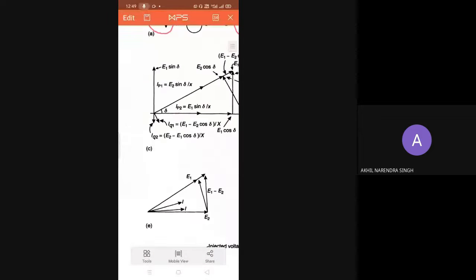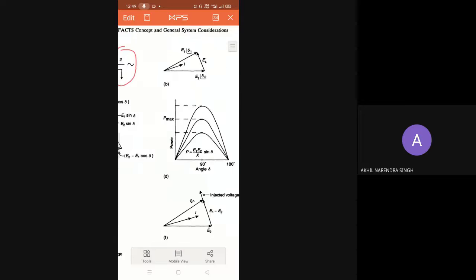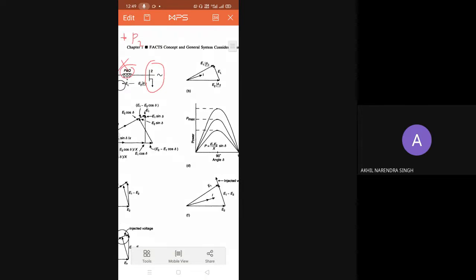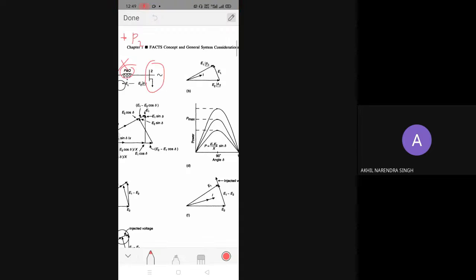As per this equation, I already told you that if we want to control the power flow through the transmission line, that can be controlled either by controlling the magnitude of E1, or the magnitude of E2, or by delta. Now how it can be done, that is what is explained here graphically. Here they just drew one phasor diagram. For this two machine system, let's say E2 at an angle of delta 2 is the reference bus. With reference to that, the E1 phasor at an angle of delta 1 has been drawn, and the difference between E1 and E2 is nothing but the voltage drop across the transmission line, that is EL.